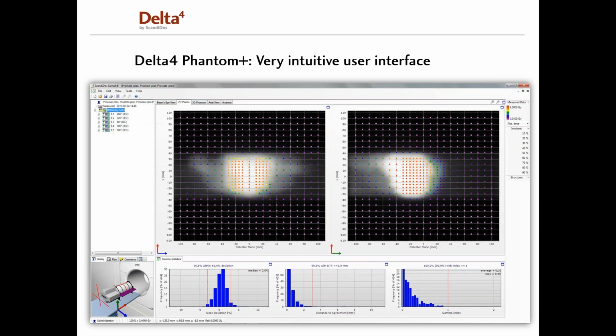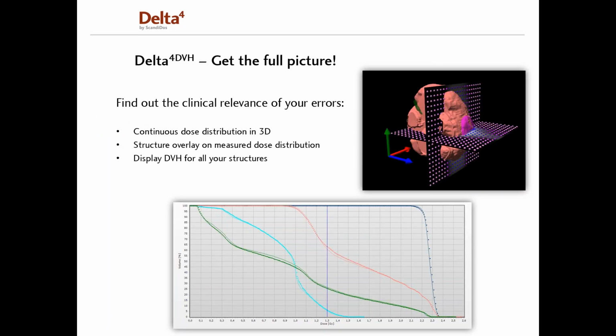Since we perform our measurements in the target region, the relevant dose is available directly after the radiation has been delivered, without the need for any calculations. The delivered dose is automatically compared against planned dose and analyzed according to your user-definable pass-fail criteria. I will show you more about the interface of the software during the demo. But for now, I would like to briefly talk about the different software options we provide, starting with the Delta4 DVH.